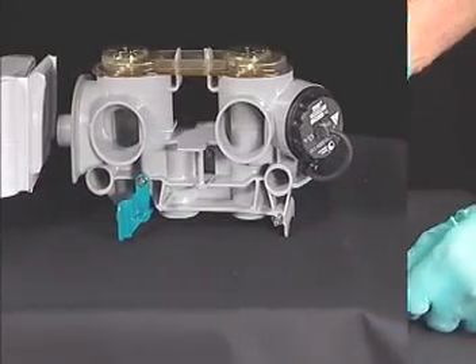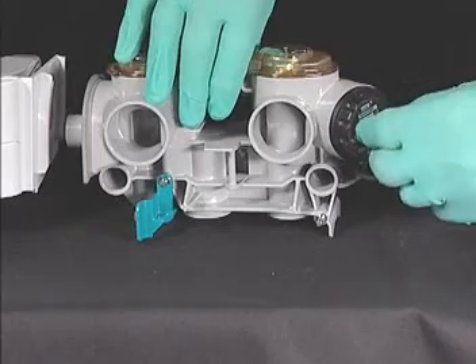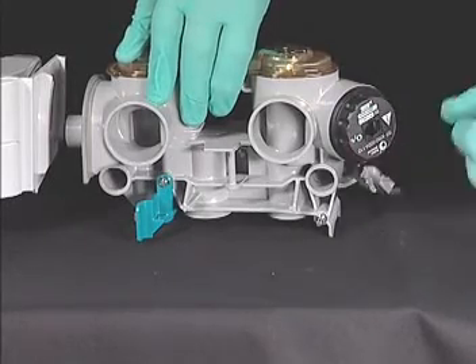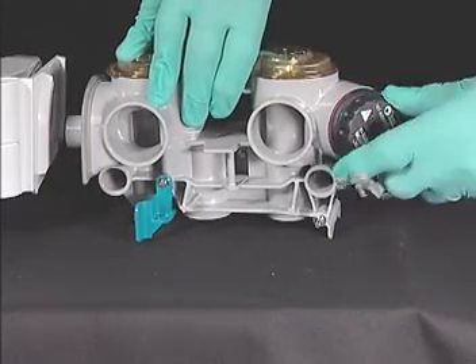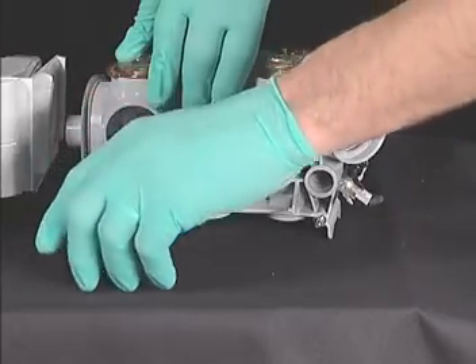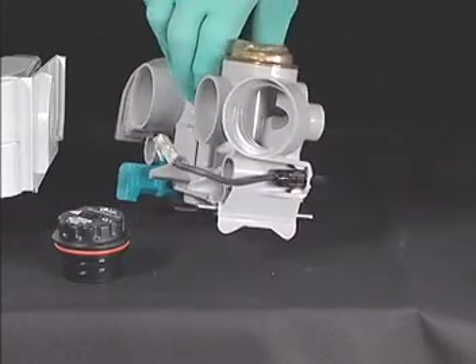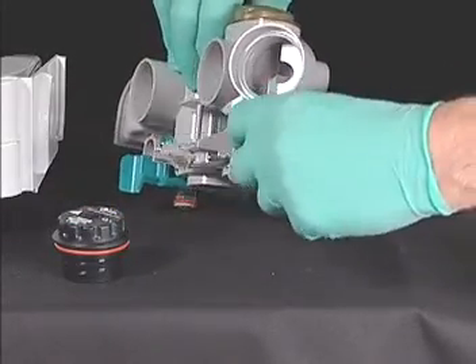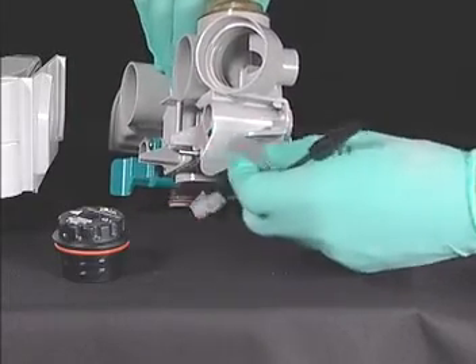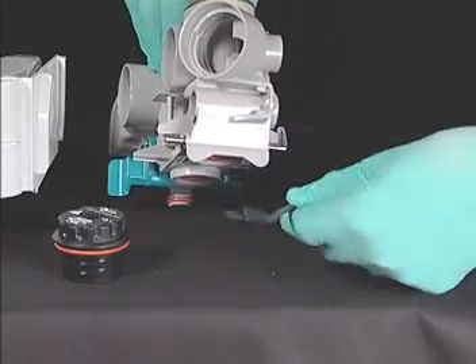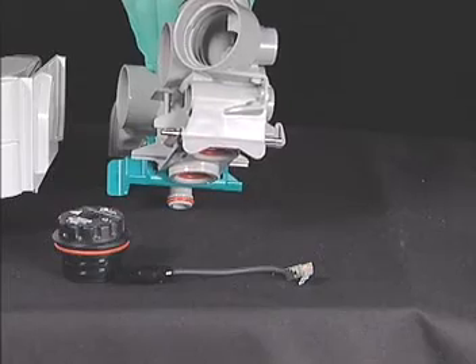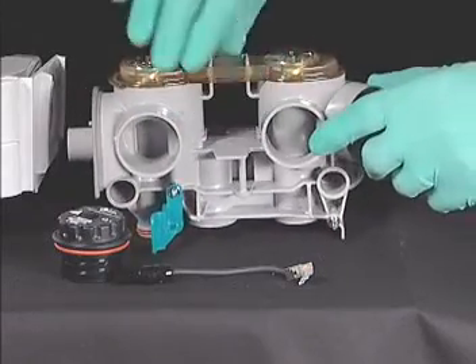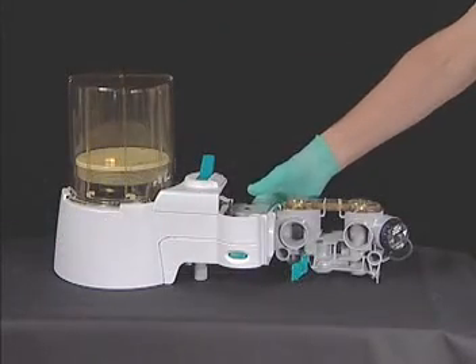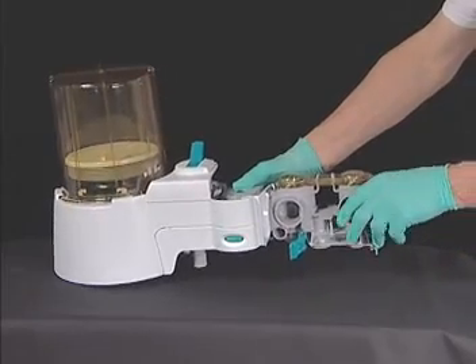Next, remove the O2 cell from the circuit module by unscrewing its cell. Also, disconnect the cell communications line by unclipping it from its harness. The O2 cell and cable cannot be cleaned or autoclaved. If desired, the flow sensor cover can now be reconnected to the ABS. Further disassembly of the ABS is possible.